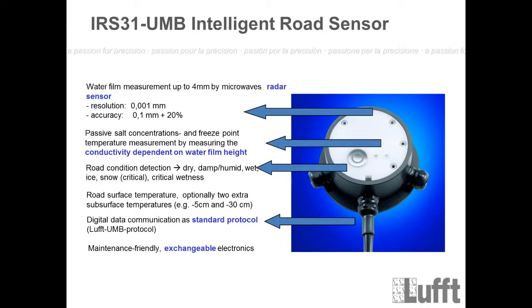So you see that here again, it's the first part, water film measurement up to 4 millimeters by microwave radar sensor. Resolution is 1 micrometer. It's a real accurate sensor here with an accuracy of 0.1 millimeter plus 20%. The second important measurement for the calibration on site is the freezing point detection, right? And of course also the salt concentration measurement.